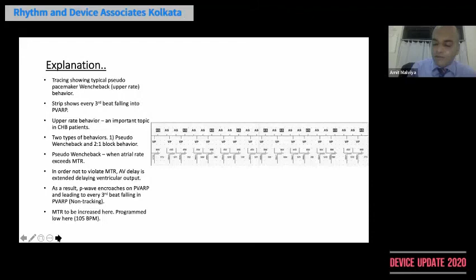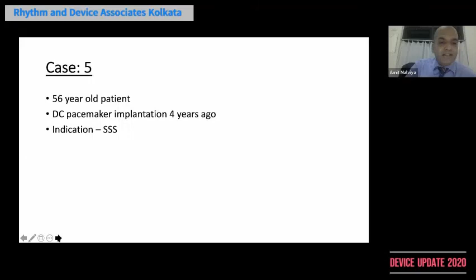So every subsequent third or fourth beat would fall in the post-ventricular atrial refractory period, and the ECG will show a Wenckebach phenomenon. So there is nothing to worry about. The best solution for this is to increase the maximum tracking rate in the pacemaker settings, and this problem will go away.